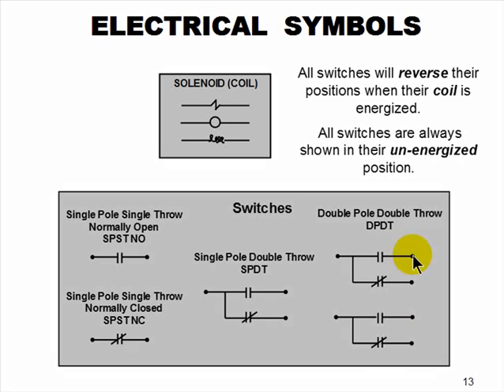This is double pole, double throw if they're mounted on the same base. I have 2 different power sources I can bring in, and each of those power sources has 2 different options of throwing. So it's double pole, double throw. If they're not on the same base, the other thing you can do is call that 2 single pole double throw switches. This is 2 of these. But if these switches are mounted on one base with one coil, then it's double pole double throw. Otherwise, single pole double throw. That's the way the switches work. They're shown unenergized, just like this. When their coils are energized, the switches change position.